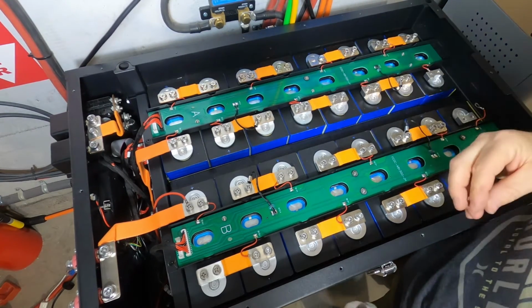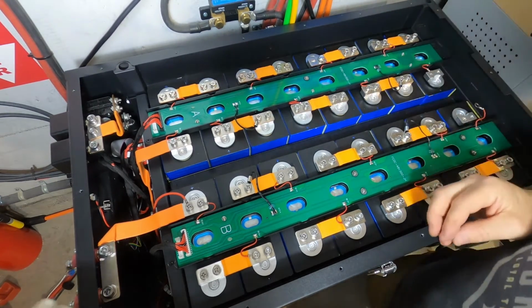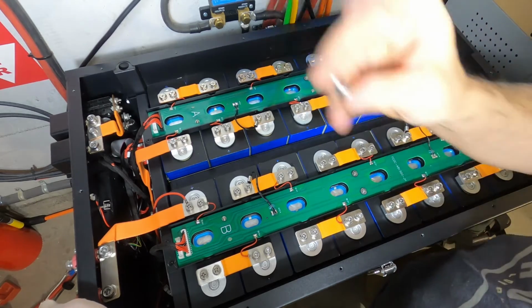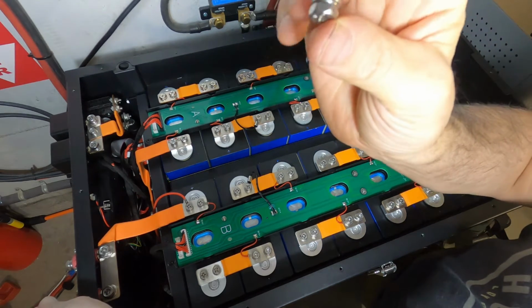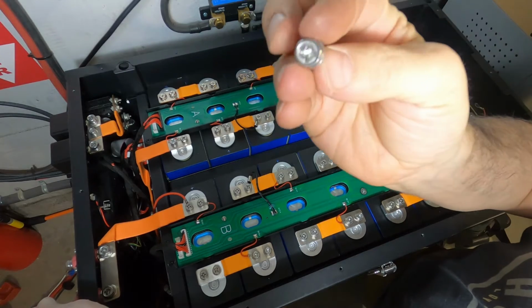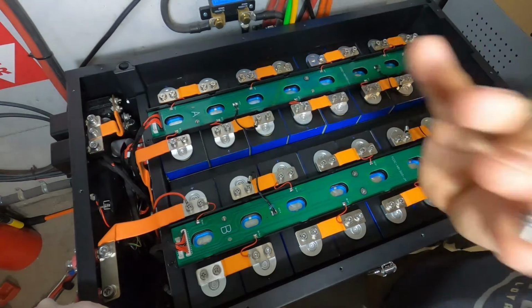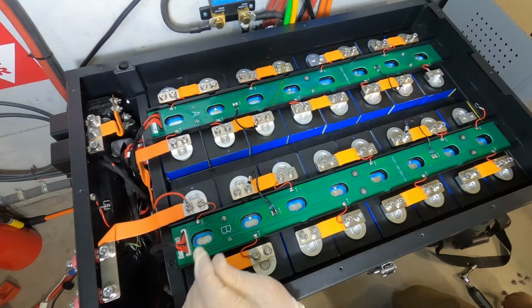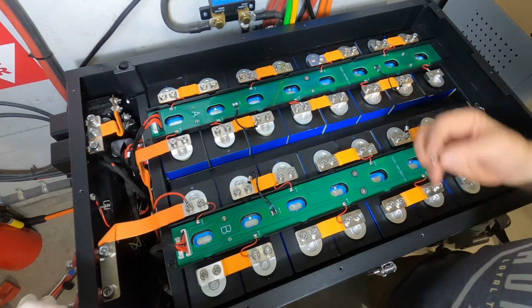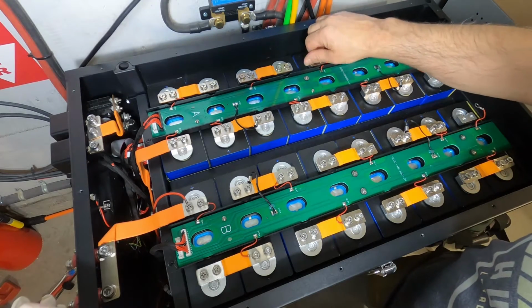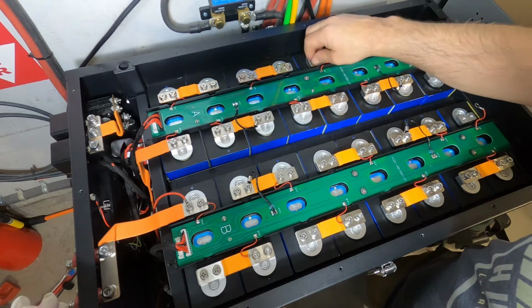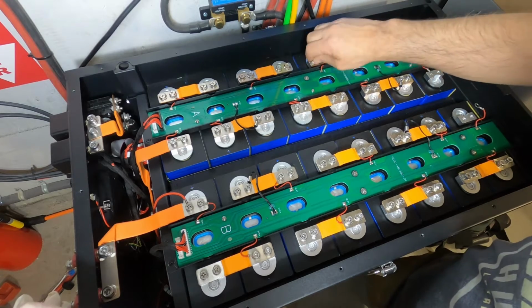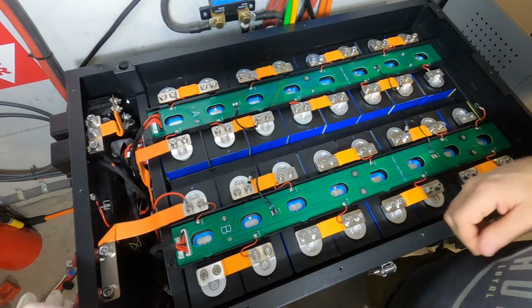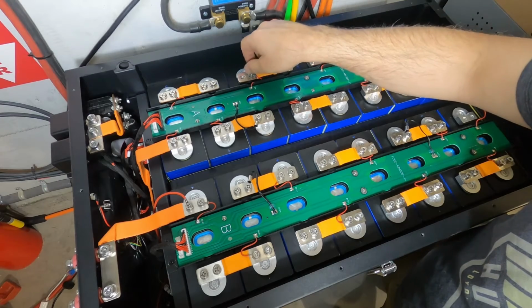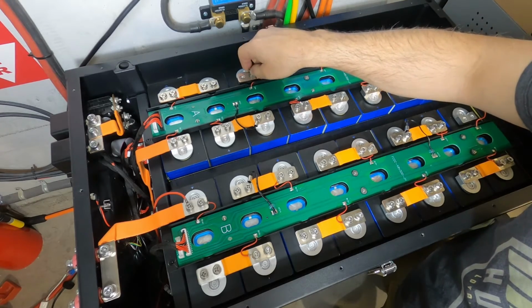But if your battery is going to be in a high vibration or mobile application, you might consider using the bolts with the lock washers, because they hold better in that type of environment. However, be aware that they do garner more heat at high amps - anything over about 100 amps, they'll start to get pretty warm. I'll put a link to that testing video down below.